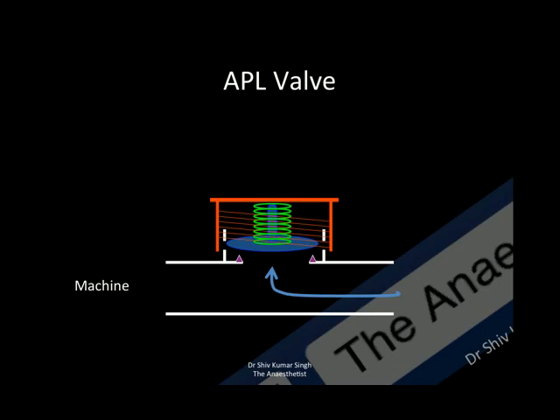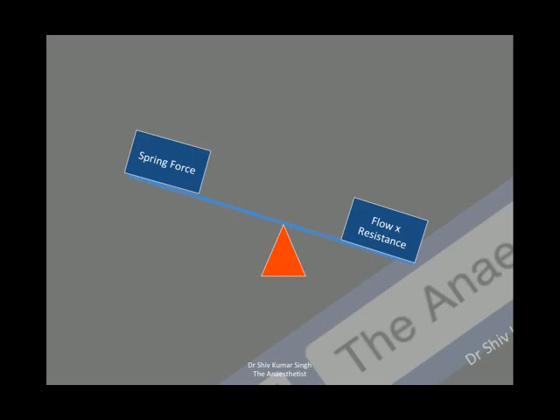This pressure acts on the disc, and the force acting over the disc area supplied by the spring creates a pressure which must be balanced by the pressure created by the expiratory flows. When the pressure generated by the fluid flow exceeds the pressure generated by the spring on the disc, the disc will be lifted up and the gases will be vented out. Essentially, the spring force on the diaphragm is balanced by the flow of expired gases and the resistance within the tubing.